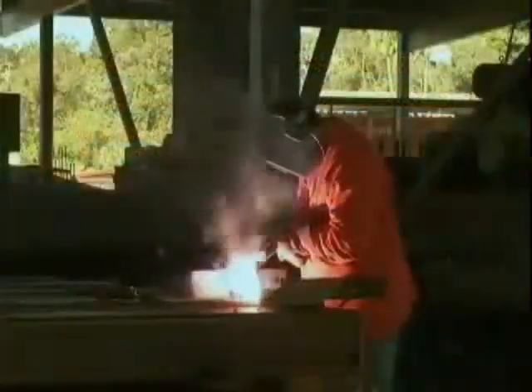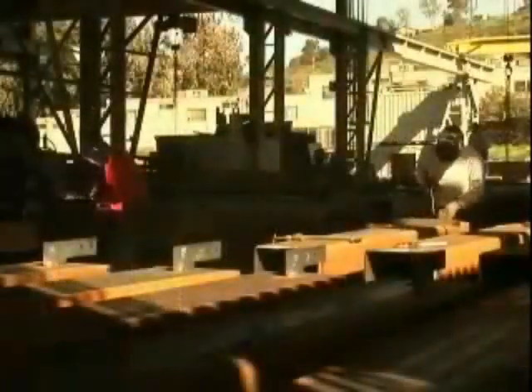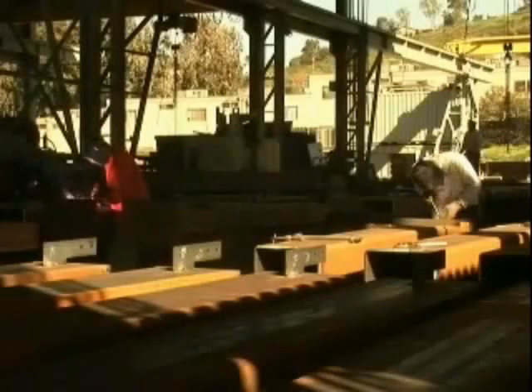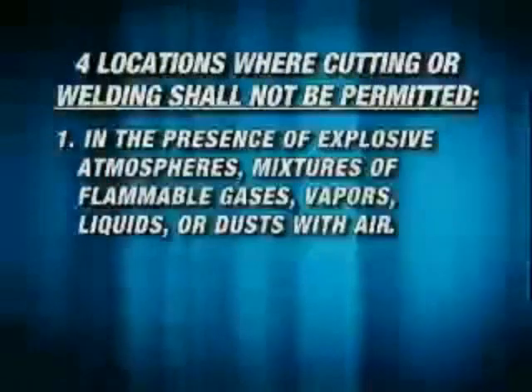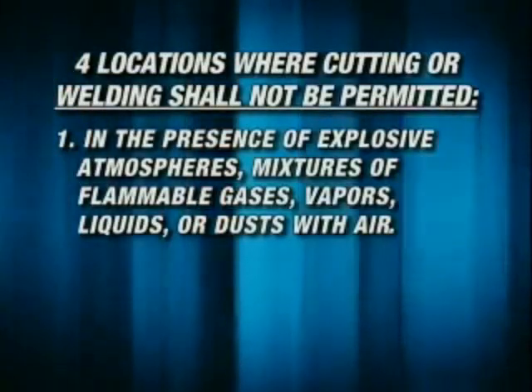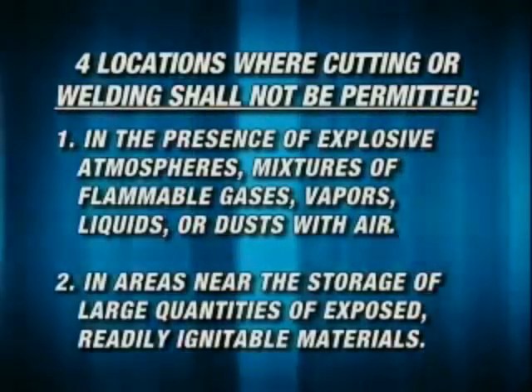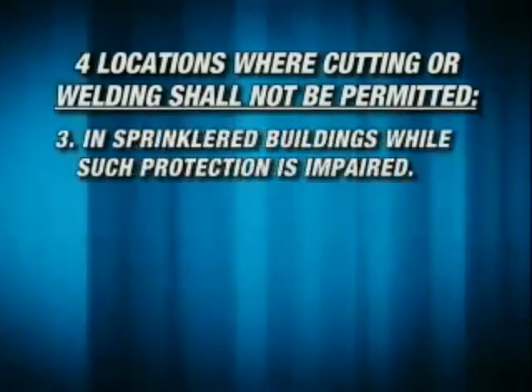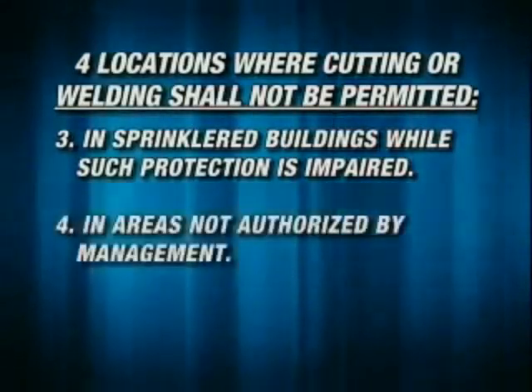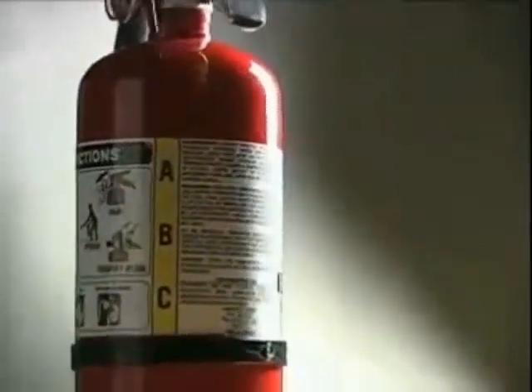Because of the hazards created by welding and cutting operations, great care shall be taken in determining work sites so they do not create fire hazards or endanger nearby workers. OSHA lists four locations where cutting or welding shall not be permitted: in the presence of explosive atmospheres; in areas near the storage of large quantities of exposed, readily ignitable materials; in sprinklered buildings while such protection is impaired; and in areas not authorized by management. It is good practice to provide each welding booth with a Class B and C fire extinguisher of a dry chemical, multi-purpose, or carbon dioxide type.